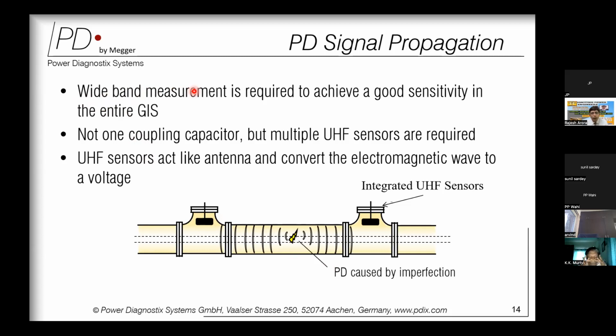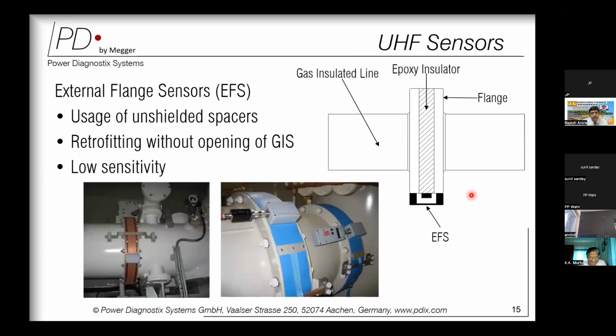And here, not a single coupling capacitor is used like in a conventional PD measurement, but multiple UHF sensors, as we see out here, are placed inside the GIS or embedded into the GIS, and are used for this electromagnetic waveform measurement. These UHF sensors act like an antenna and convert the electromagnetic wave into a voltage signal, which is ultimately fed to the measuring instrument.